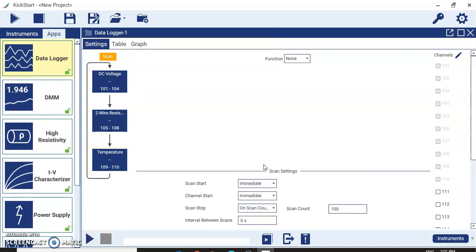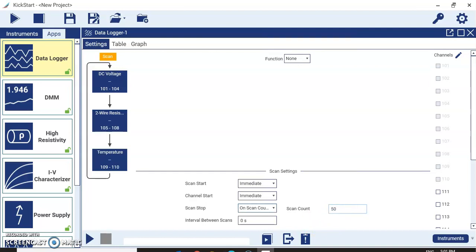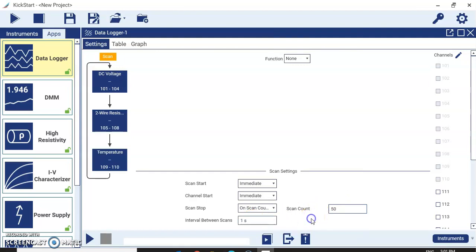So I have completed all the settings — measuring voltage, resistance, and temperature across channels 1 to 10. There is also a scan setting where you define when to start and stop logging data. Options include stopping on scan count, after a duration, or never. I will select scan count, log 50 readings, with an interval of one second between scans. Now we are ready — just click Run App and it will start acquiring data. You can see the progress: 0 of 50, 1 of 50, 2 percent complete, with time remaining shown.